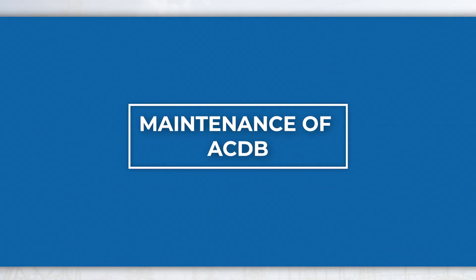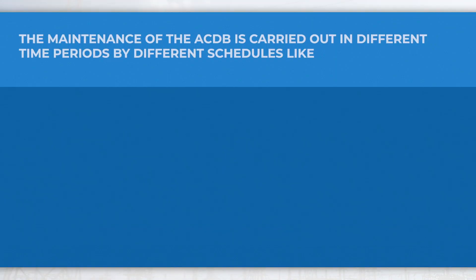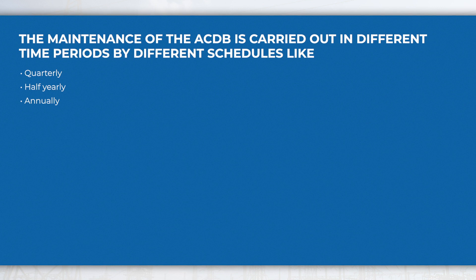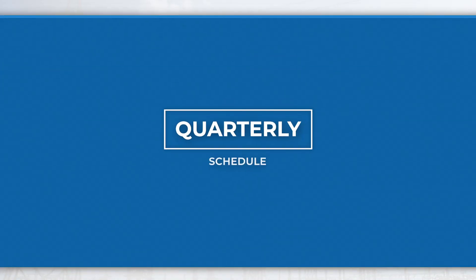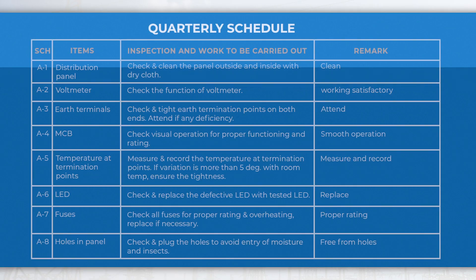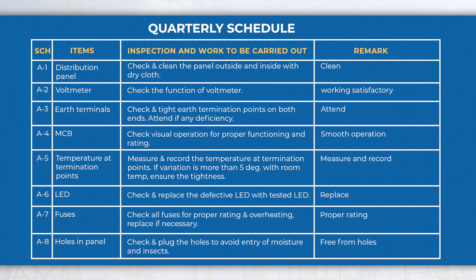The maintenance of the ACDB is carried out in different time periods by different schedules like quarterly, half-yearly, and annually. In the quarterly schedule, perform activities like measuring the temperature at termination points and checking the condition of fuse, etc.